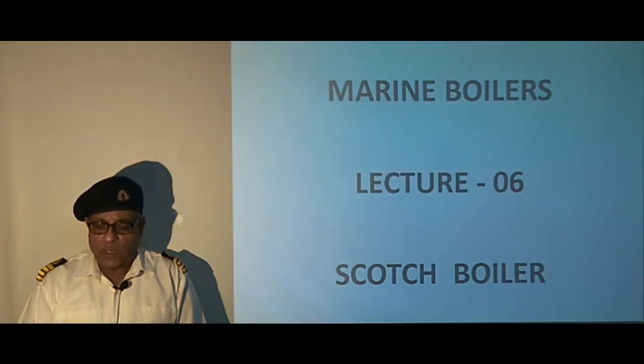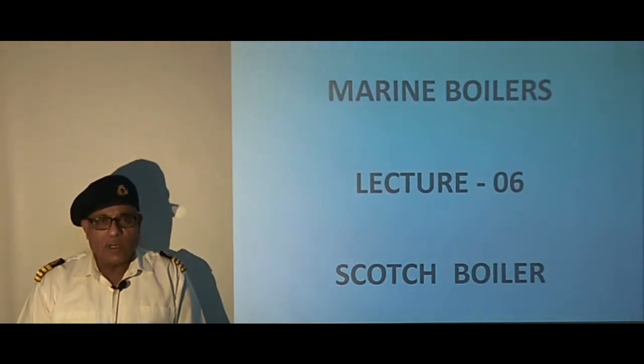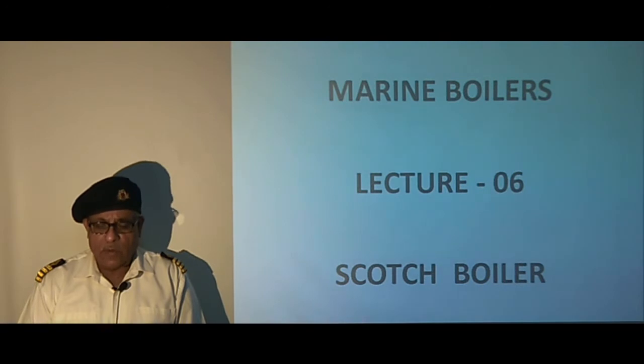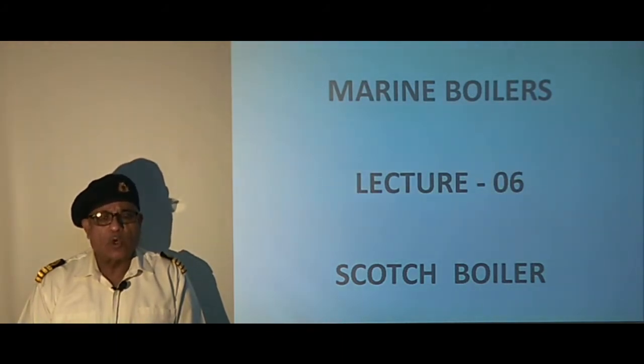Scotch Boilers is one of the earliest boilers used on steamships. Being a low pressure boiler, it was used for auxiliary purposes. Early boilers had riveted construction but later boilers were fabricated by welding. It is a fire tube type boiler with horizontal design. As horizontal designs consume more space, it is not preferred on motor vessels nowadays.